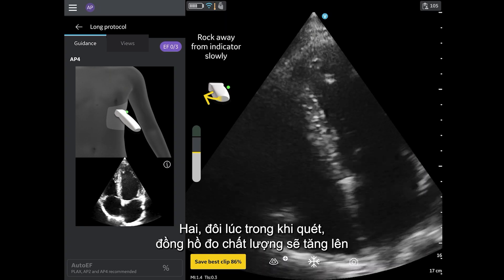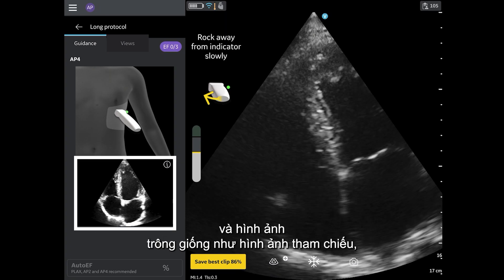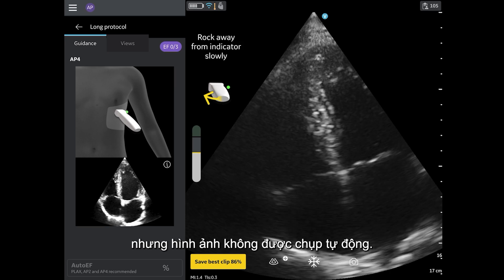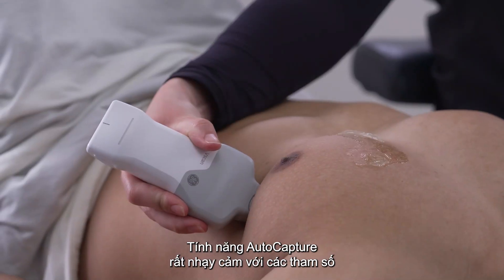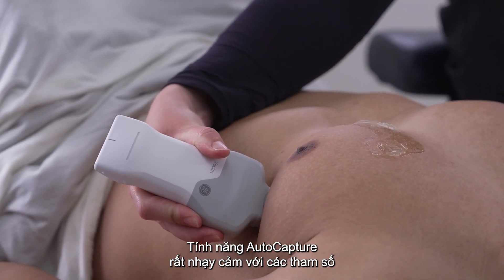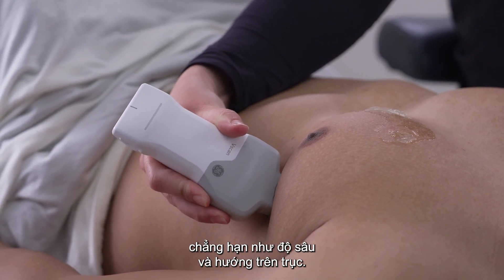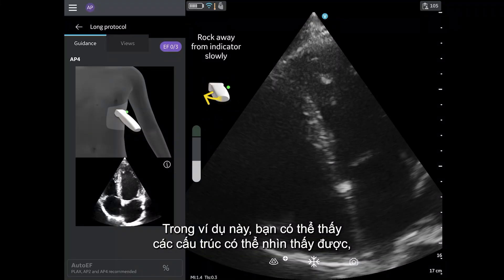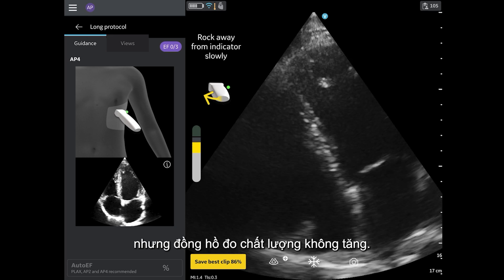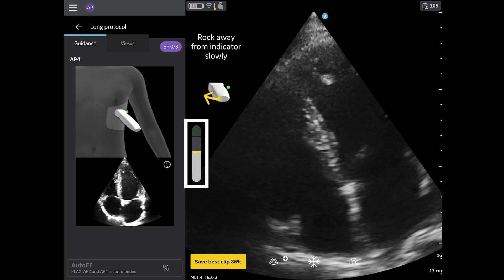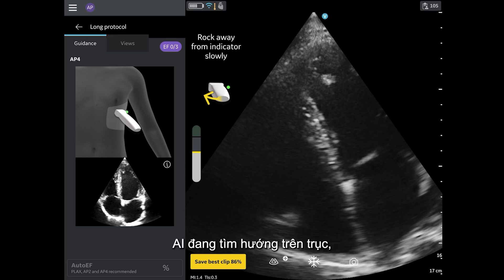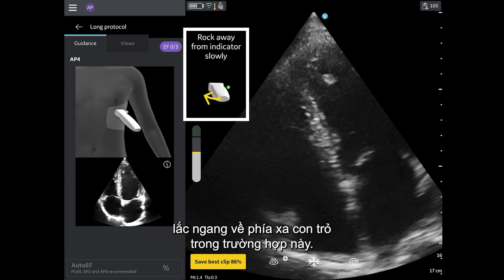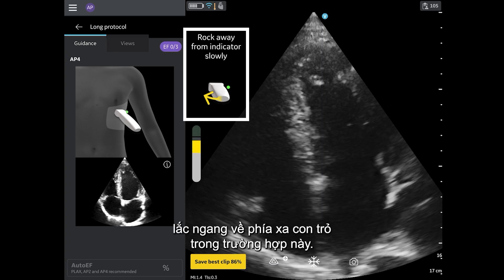Two, sometimes when scanning, the quality meter will rise and the image looks like the reference image, but the image is not auto-capturing. The auto-capture feature is highly sensitive to parameters such as depth and on-axis orientation. In this example, you can see that the structures are visible, but the quality meter is not going up. The AI is looking for on-axis orientation, which can be achieved by following the prescriptive guidance — rocking away from the indicator in this case.